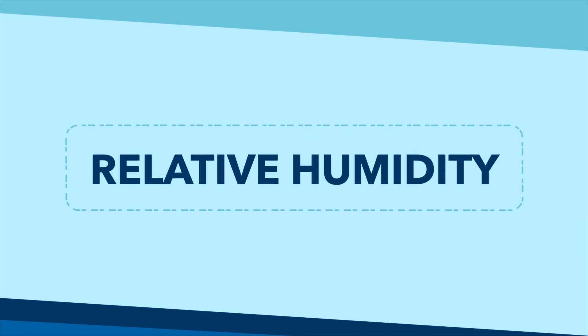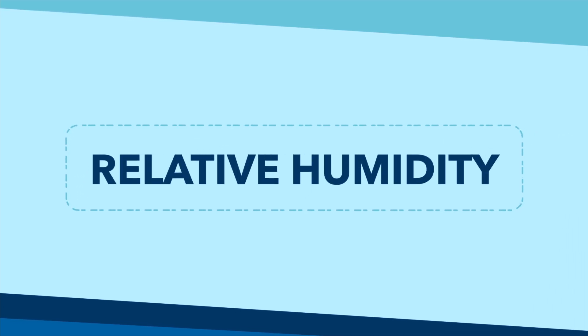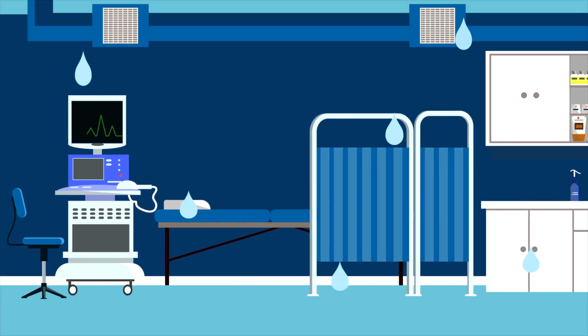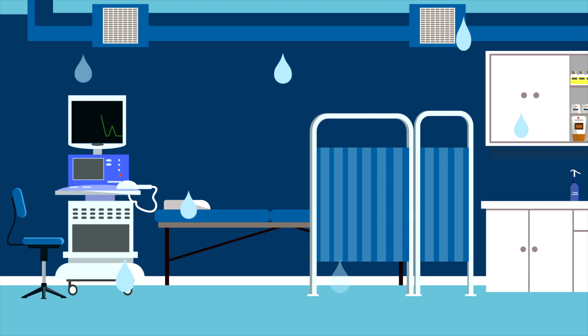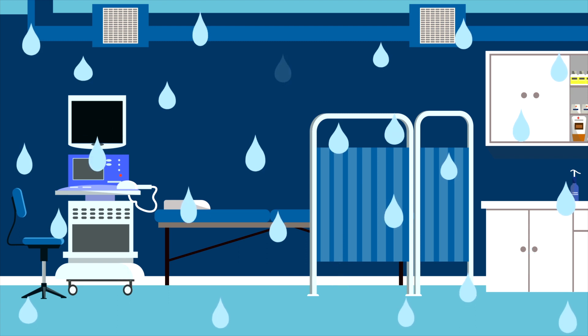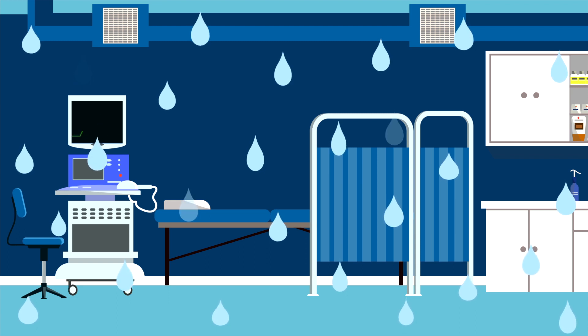First, let's clarify a few terms. When we talk about humidity in healthcare, we use the term relative humidity. Relative humidity is a ratio or percentage of how much water vapor is currently in the air versus how much water vapor could potentially be in the air. At 100% relative humidity, the air is fully saturated, meaning it can't hold any more water vapor.